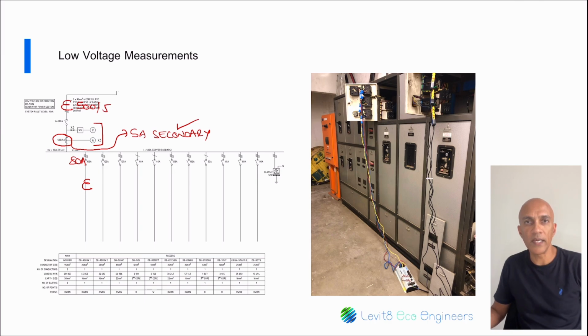For example, on an 80 amp feeder, do not use 1000 to 5 amp. It is very likely that the load on the 80 amp circuit may only be about 20 to 30 amps. And using a clamp with too high a rating may give resolution issues, resulting in poor accuracy. Using up to 250 to 5 amp is probably the most I would go with. However, it does depend on your instrument and its capabilities.